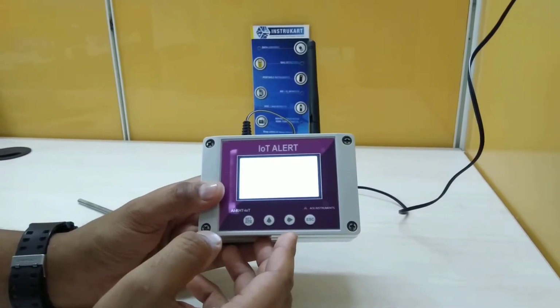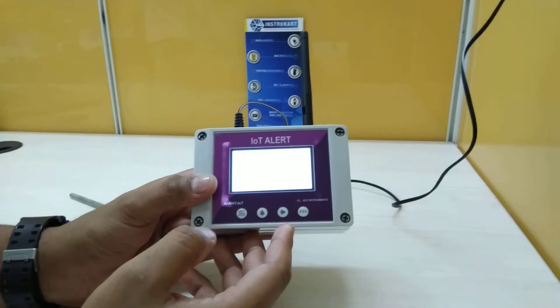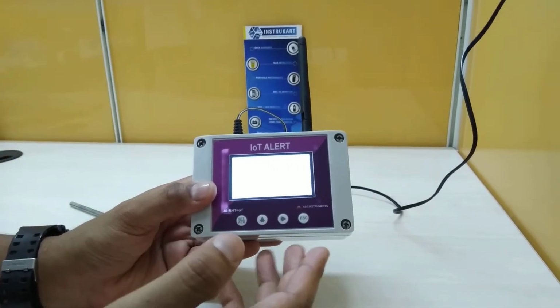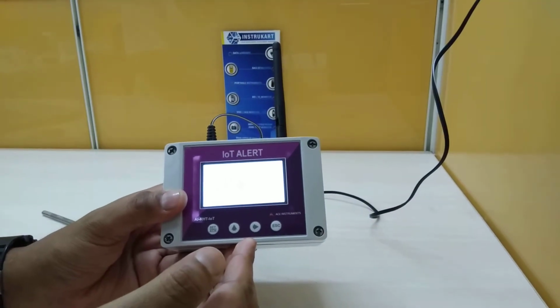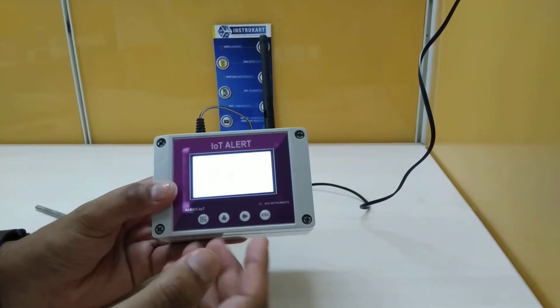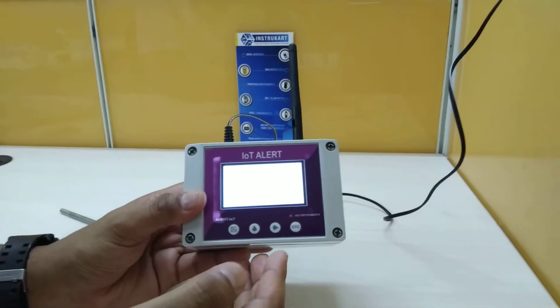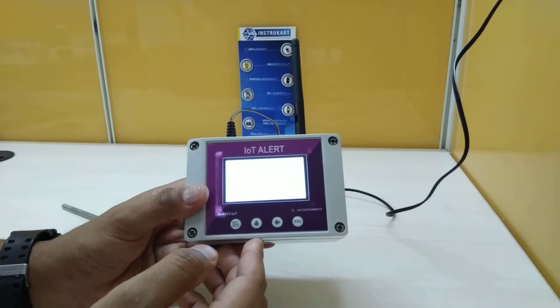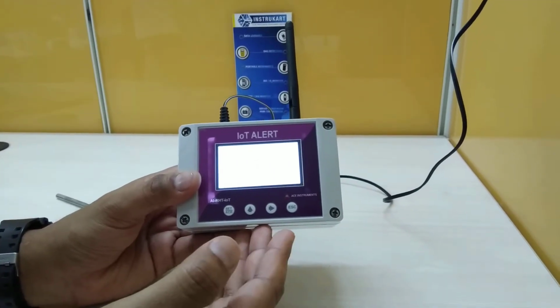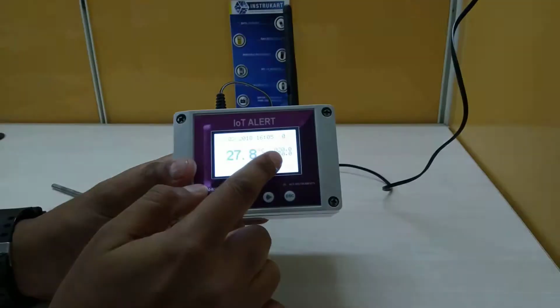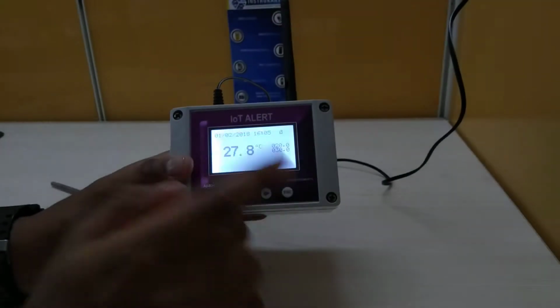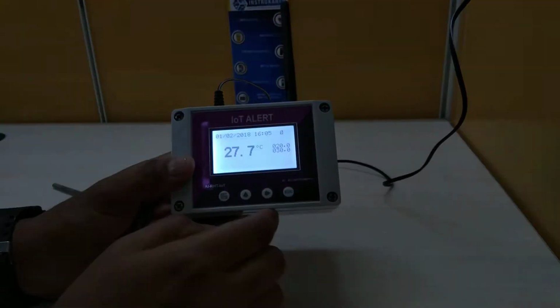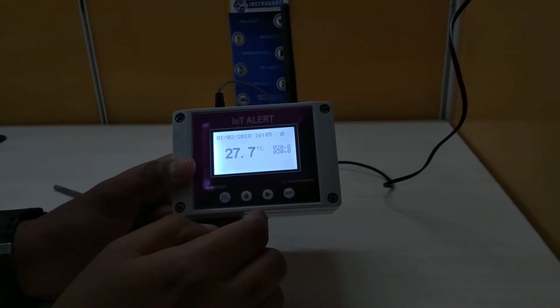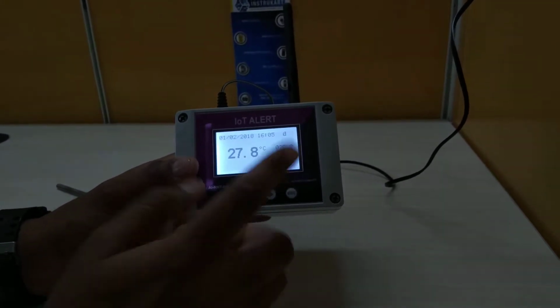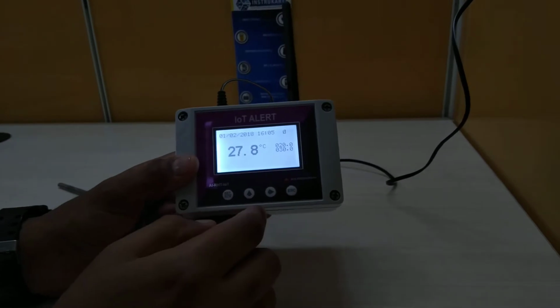Basically, we have three kinds of SMS which will be triggered. The first kind of SMS is the periodic SMS, wherein the user puts the SMS period, that is half an hour or 1 hour frequency, and the SMS will be sent to five numbers for the current temperature. The second type of SMS is the alert SMS. Whenever the temperature goes beyond the set point, it will give an alert SMS to all the five numbers. And the third kind of SMS is a request SMS, wherein you can request this instrument for the current temperature through your registered mobile number, or the mobile number which you register here.